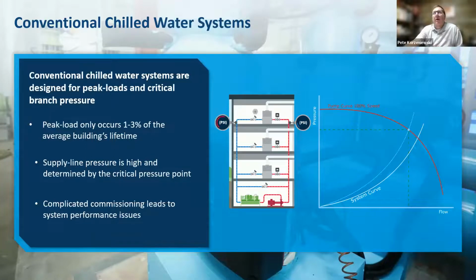All right, thank you, Justin. Just to summarize some of those points and to keep in mind, with conventional chilled water systems, and this applies to any future designs we look at, is that peak load, what we're designing for, only occurs 1% of the time typically. And as we've seen in recent news, Sacramento saw 115 degrees the other day. That may be a new design point, or maybe something a little less than that, but we're going to design systems for that, but they spend very little of their time operating there.